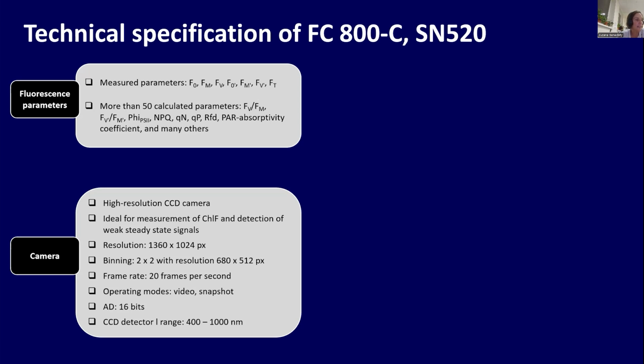If you have samples that are very weak in signal, we can use a function of the camera called binning, which in technical terms is something very well known. You simply count together pixels 2 times 2. So of course you decrease resolution from the original full resolution to 680 times 512 pixels, but you increase the signal 4 times. So this is a kind of trick that can be used for very, very low signals eventually, but I haven't used it for a few years.